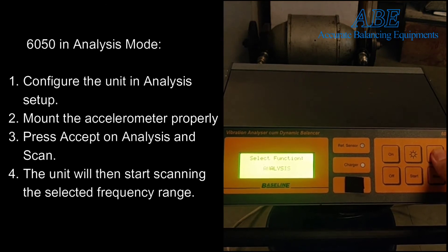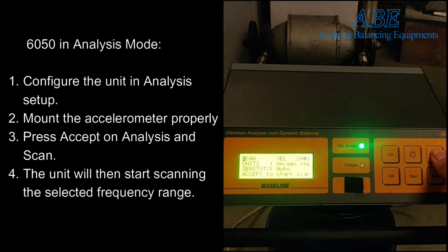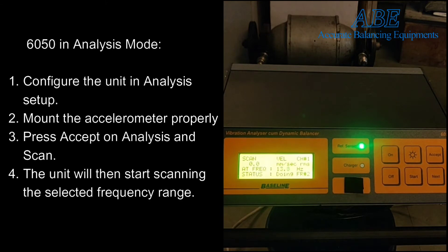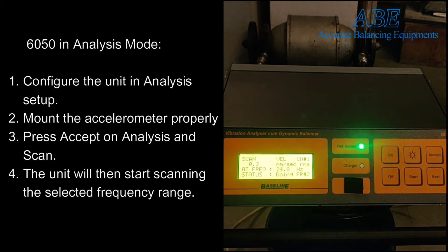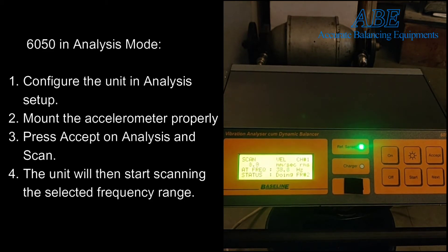The 6050 features automated full frequency analysis. Frequency analysis can be done over the frequency range 1 hertz to 10 kilohertz, 60 CPM to 600,000 CPM. Its microcontroller scans the entire frequency range looking for spectral peaks. Each peak contains valuable information: the magnitude of the peak is the severity of the vibration, and the frequency is related to the nature of the defect.